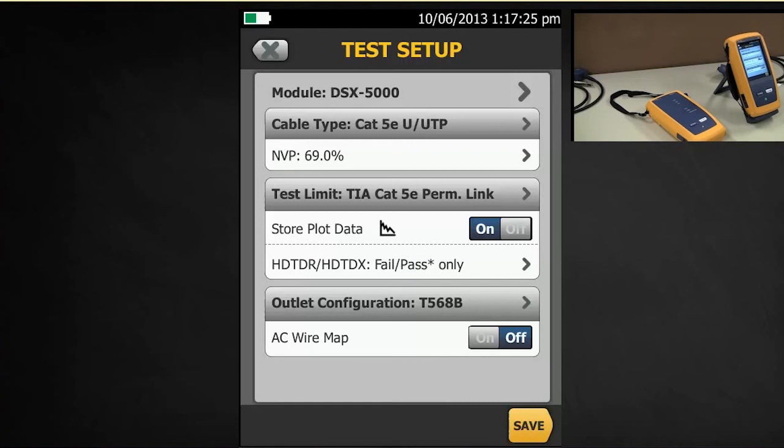If you do turn that on, you're going to disable the resistance and the shield test because those are two tests that cannot be done through a mid-span device. And you will get a warning if you do turn that feature on.